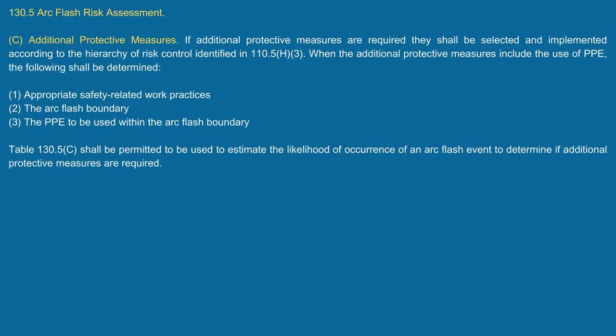Now, it has to be justified energized work too through the other. Sure. A lot of people don't realize that if you can't do a scheduled shutdown on that, then you have to justify why you can't do that scheduled shutdown. Sure, that's right. But at least they have items that are listed in place for that, if you can.